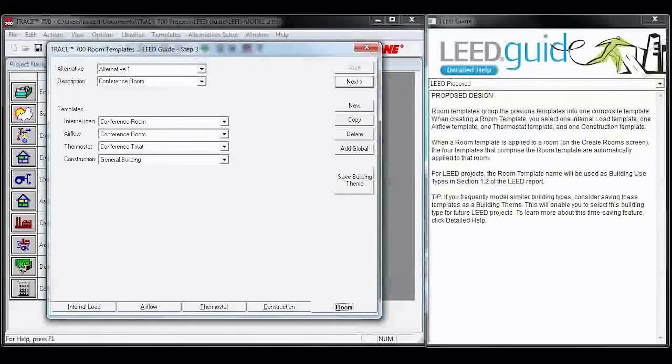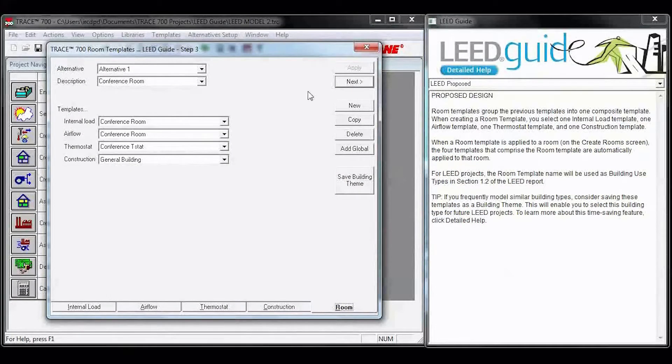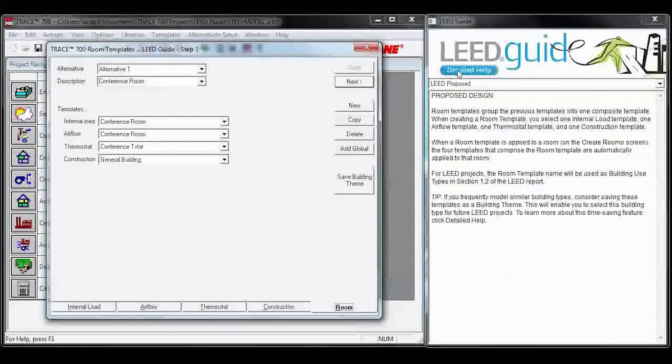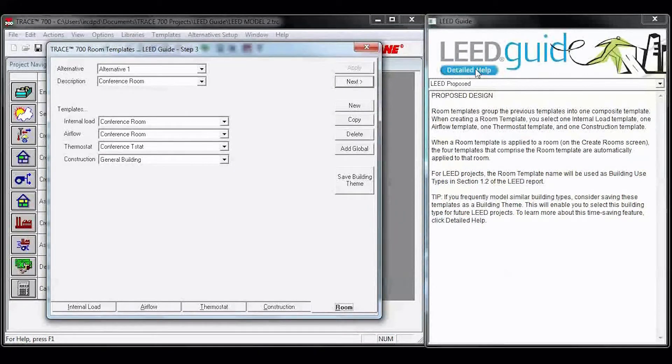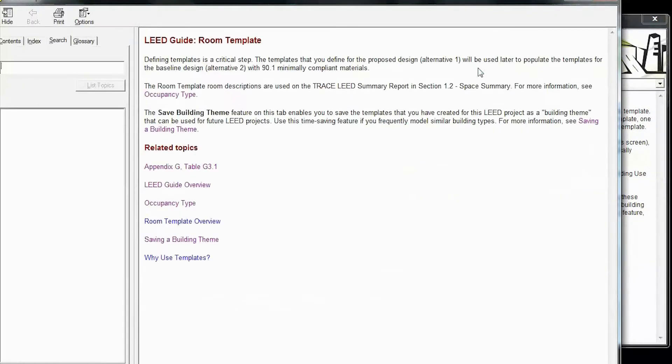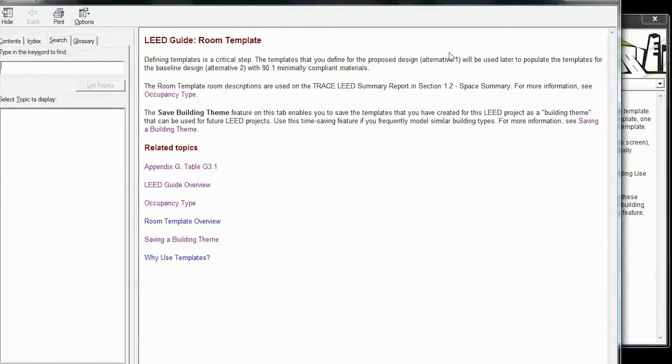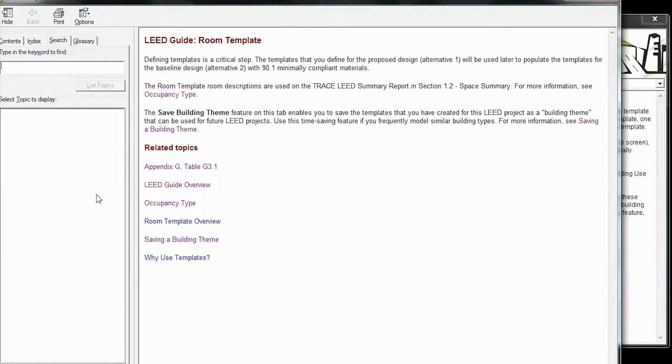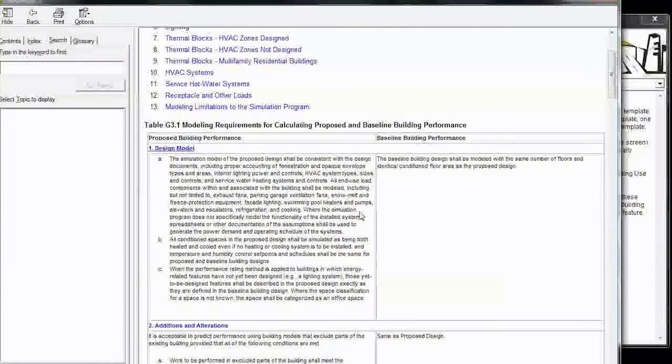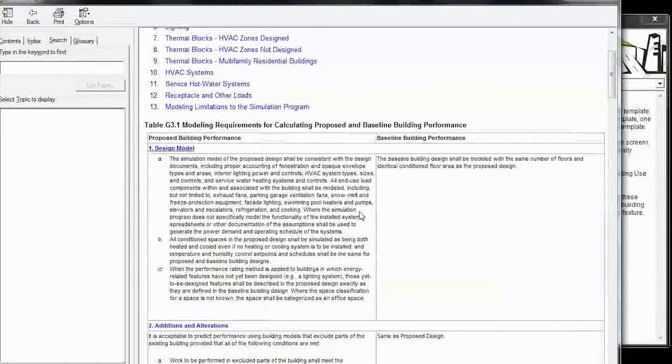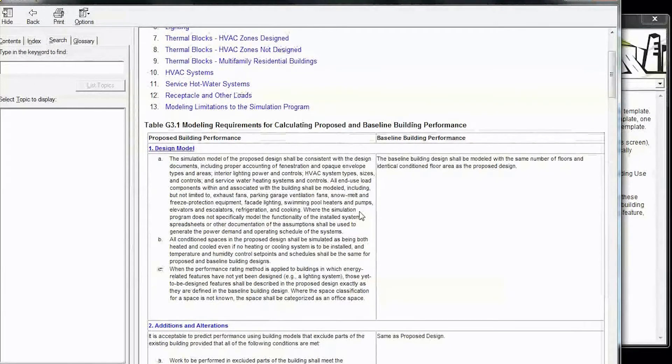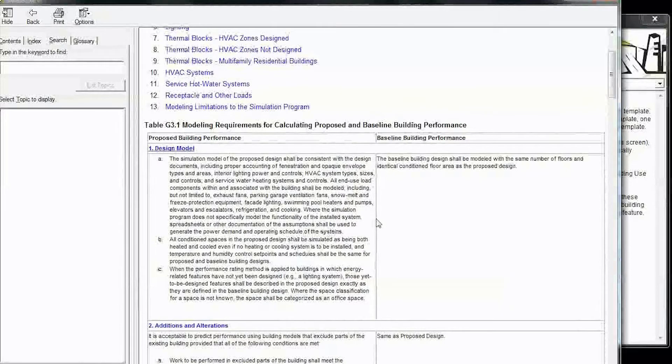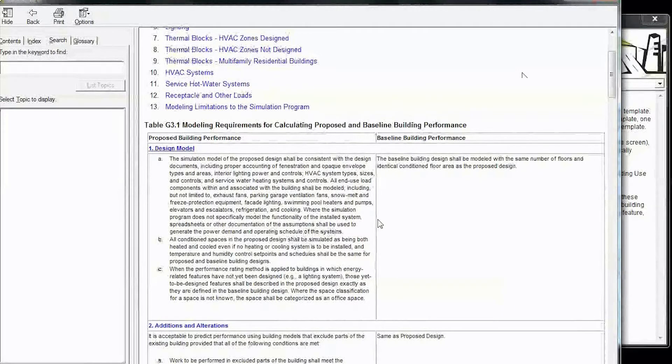Once you've completed all of your templates, you can hit Next here. One thing I want to point out is the detailed help for the LEED guide. This opens a new screen and it gives you information regarding the tab that you're on. It also has related topics. One of the most useful things that we've added is Appendix G Table 3.1. This will show you side-by-side comparison of how you need to model the baseline and the proposed according to Appendix G.